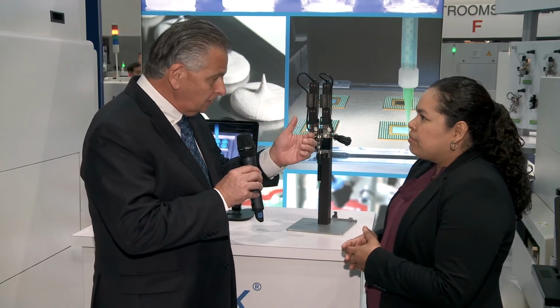Looking at the progressive cavity pump, the rotor is a metal-based product inside a rubber-based stator. The rotor inside the stator is slightly larger than the stator, because you want to form a perfect seal. That perfect seal allows you to achieve high volumetric accuracy.